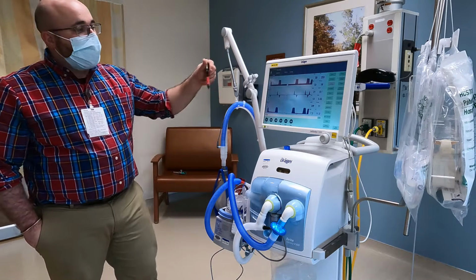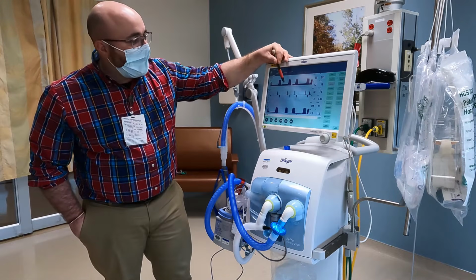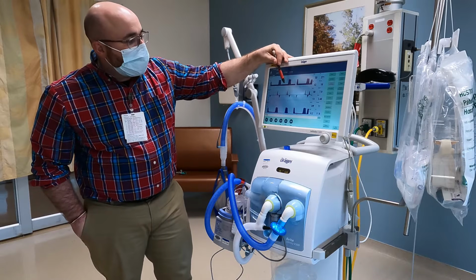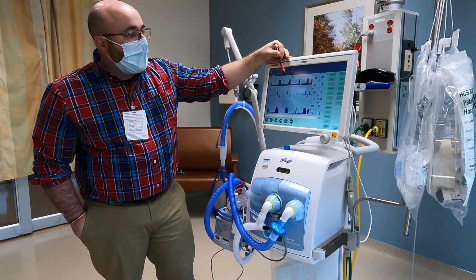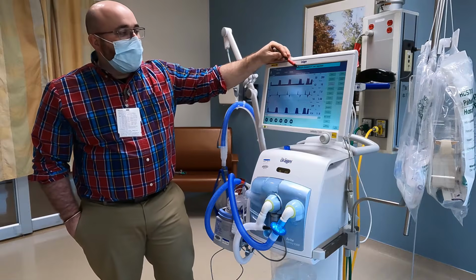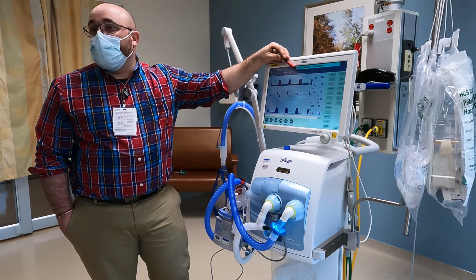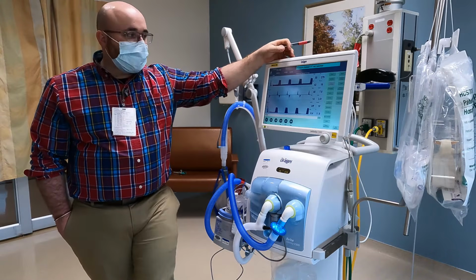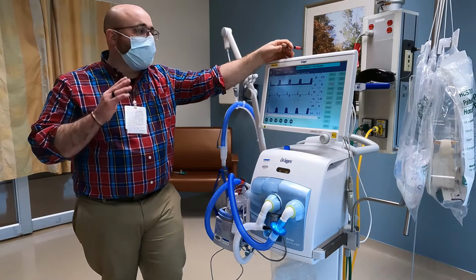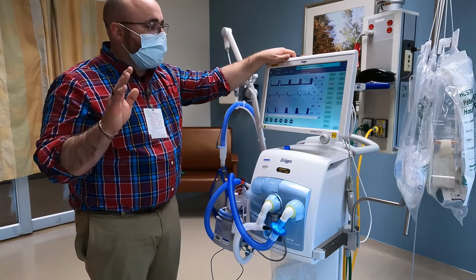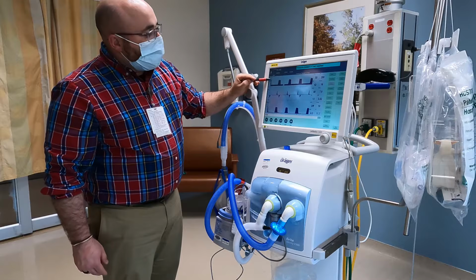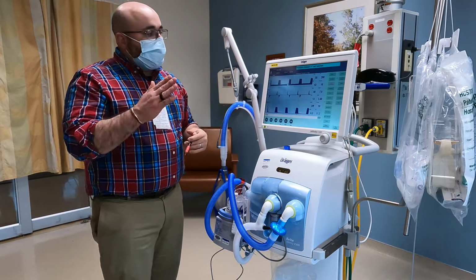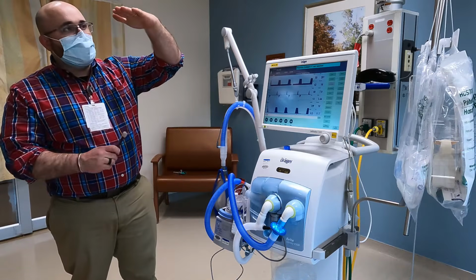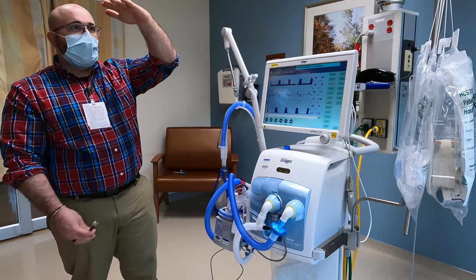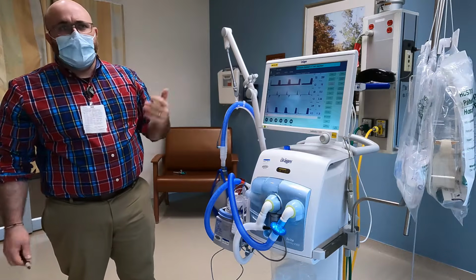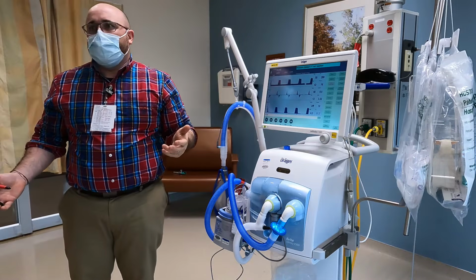Now, what this vent's gonna try to do now that I got rid of that, it's gonna try to shoot to that tidal volume we have for a few breaths, but when it can't, it'll come up with this. So it just beeps like that? Yes, it just beeps like that. Because in the olden days, the old vents, if your peak pressure, that red line, was set at 40 or 45, the vent would go hit it and stop, hit it and stop. You'd be given like 25 mLs for a breath.